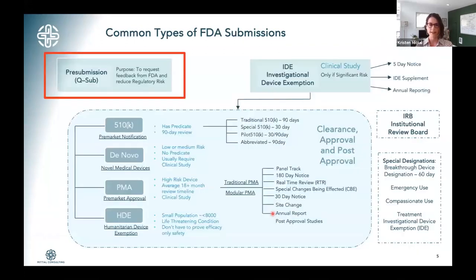Now let's get a little bit deeper. Let's go into the common types of FDA submissions. On the previous slide, I talked a little bit about 510Ks and PMAs, and these are probably the most common types of submissions you're going to run into for most generally class 2 and class 3 devices. But as you can see in this large blue box here, there's a lot of other types of submissions you can do to the FDA as well.